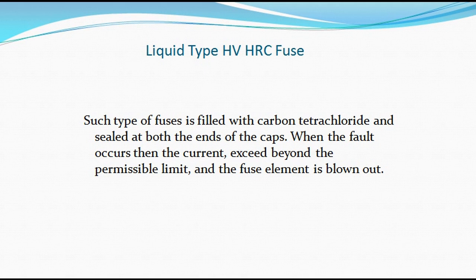They may be employed for transformer protection and backup protection to the circuit breaker. What I'm trying to explain here is that this liquid type has a liquid inside of it, and that liquid acts as an arc quencher. Simple. And in that case, it may be employed for transformer protection and backup protection to the circuit breaker. Just as I said from the start, it is used where a circuit breaker cannot function. So that is where you can see the high voltage fuse employed, in terms of transformer protection and backup protection to the circuit breaker.